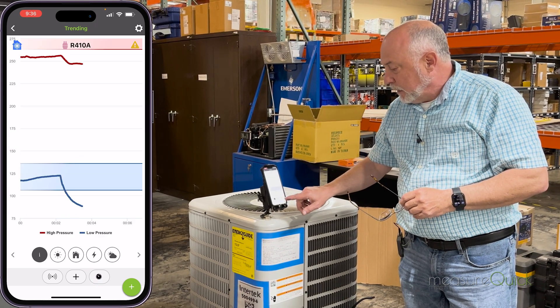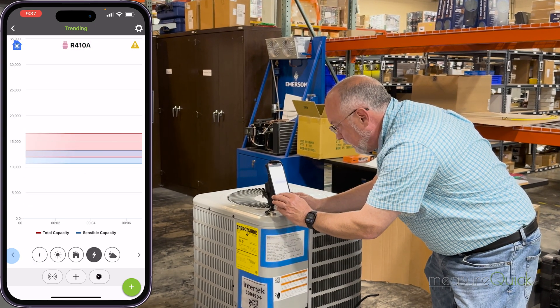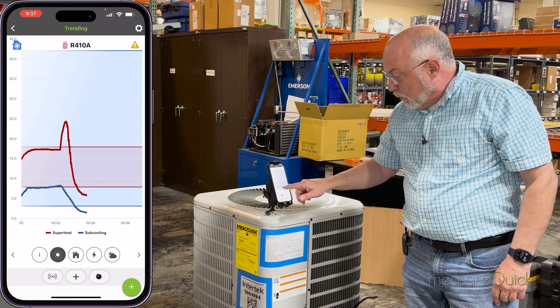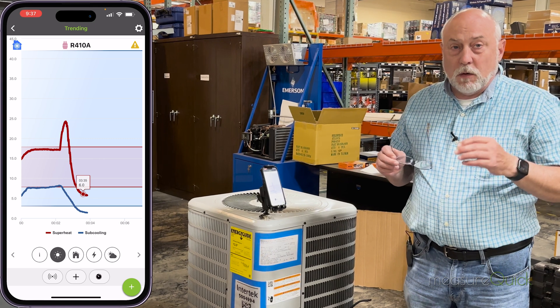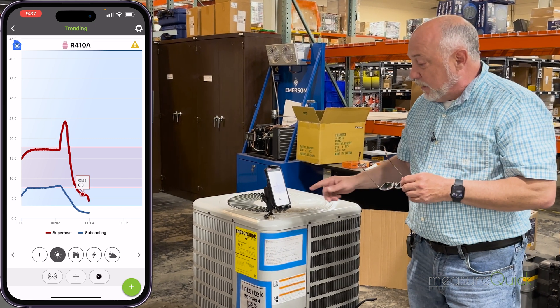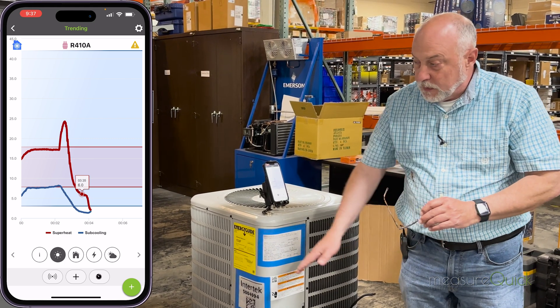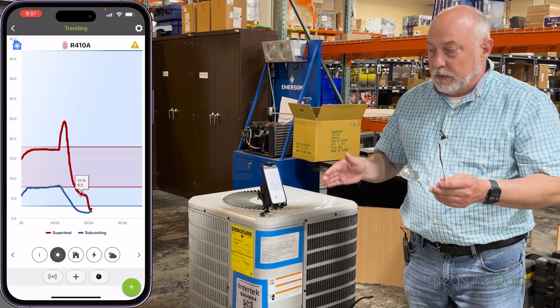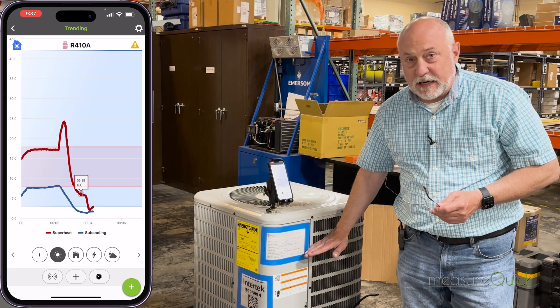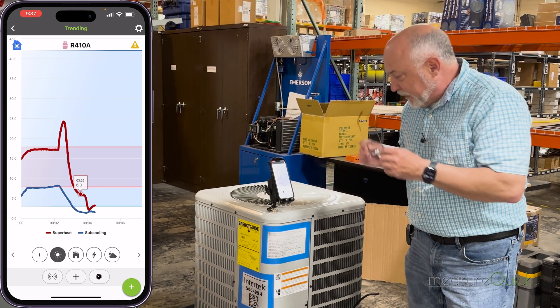Going back to our trend, you can see that our superheat went up, it came down below the target, but we're still running about 6 degrees of superheat right now. So our superheat did drop down, but the system is not flooding. What we're seeing right now is called charge migration — refrigerant is basically coming out of the condenser and going into the evaporator. There's no heat energy to boil that refrigerant away, so it's stacking in the evaporator coil and we're actually seeing it build up. That's why the superheat is going down. The condenser is starting to starve because it's not getting that refrigerant back. The charge has migrated over into the evaporator coil — a very important concept to understand. But the system is still not flooding.